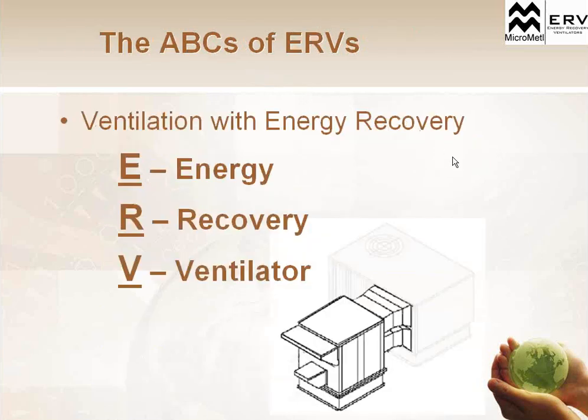So let's get started. If we talk about the ABCs of ERVs, ERV actually stands for Energy Recovery Ventilator. There's a lot of confusion sometimes in the market. There's a couple different terminologies that are used. There's HRVs in the market. There's ERVs in the market. I've seen TRVs. And basically, ERV stands for Energy Recovery Ventilator. HRV would stand for Heat Recovery Ventilator. So if you see an HRV, that actually is only going to be a sensible recovery of energy. Whereas an ERV is total energy. So it's going to be sensible and latent recovery.